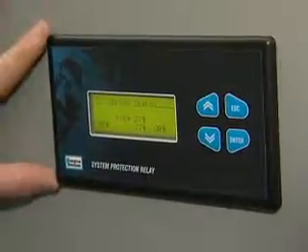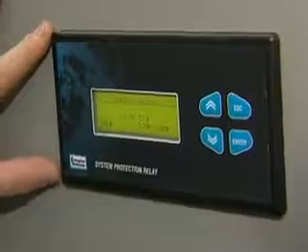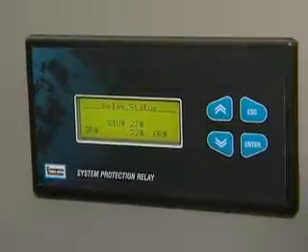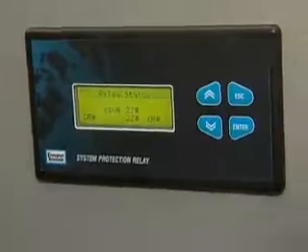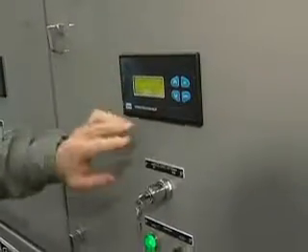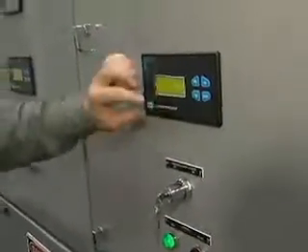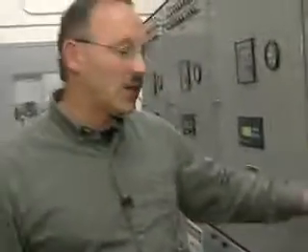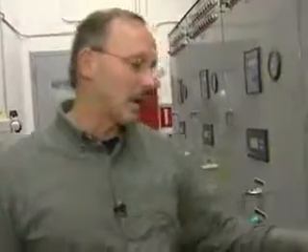In the center of this display is our protection relay. This basically protects our bus from under- and over-frequency, under- and over-voltage, reverse power, failure to synchronize, and loss of excitation on our generator ends. These are all preset items that don't ever have to be adjusted once set up in the field. Our technicians go in, program all of the settings, and test them to make sure they function properly.